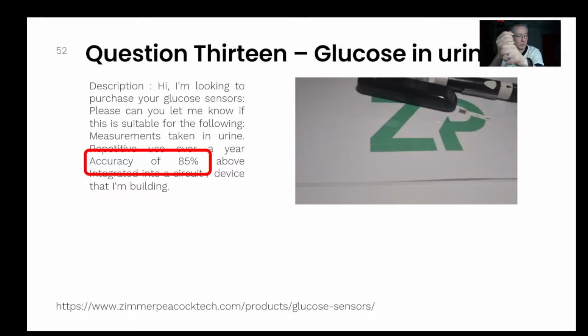So first of all, they would calibrate them there, and then they went to calibration per batch, so there'll be a QR code associated with each batch, let's say, and they in fact even had little inserts to calibrate the meter based on the sensors, but they would have batch to batch variability, and these days they're all calibration free. Great. That's a journey, and that journey has been going on for about 40 odd years, and it's easy to say that billions have gone into making them calibration free like that today. And I did you a quick demonstration.